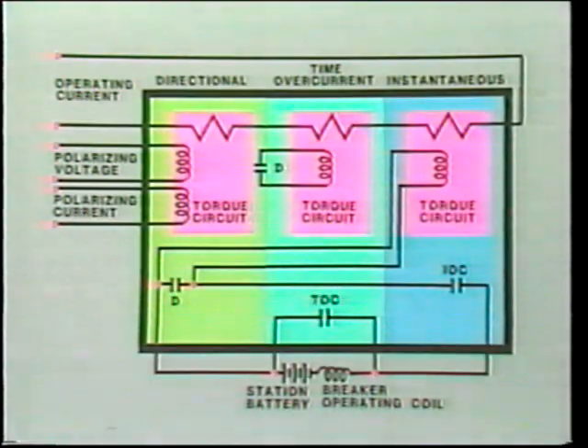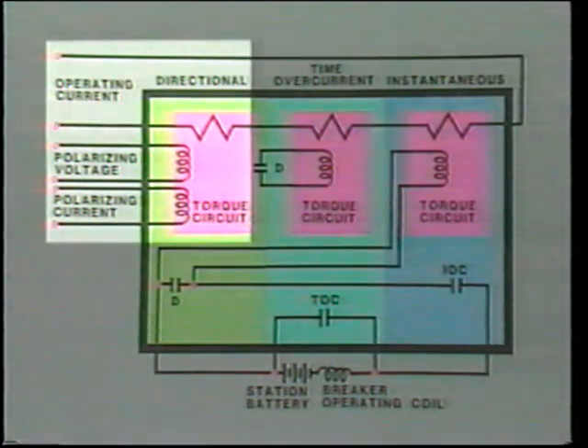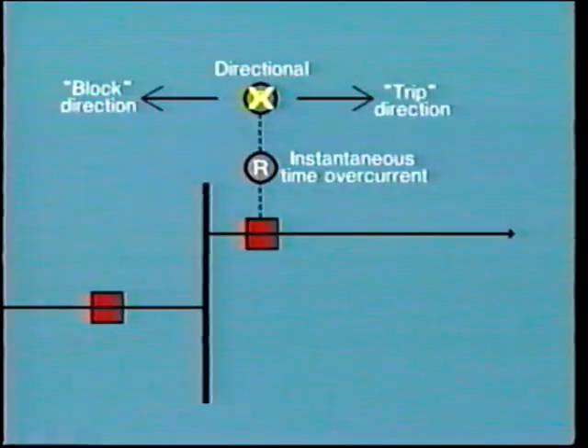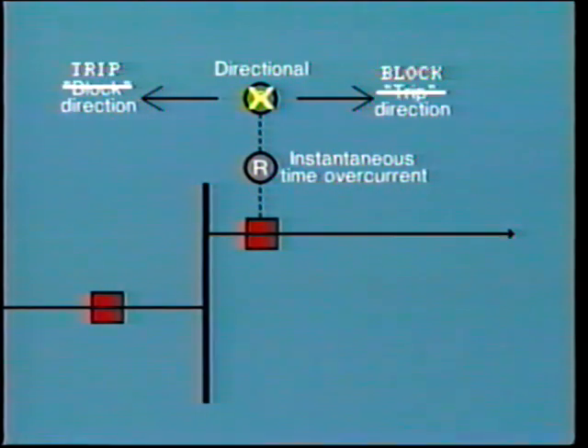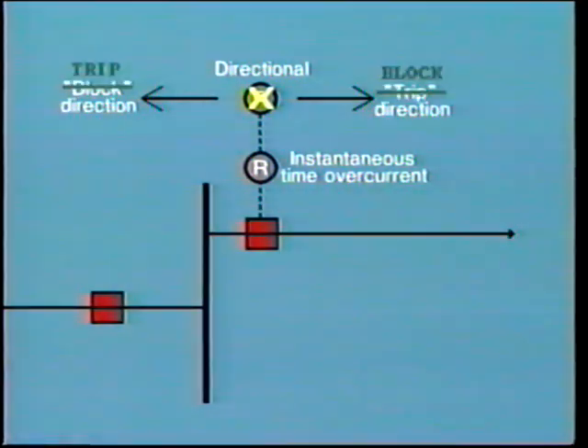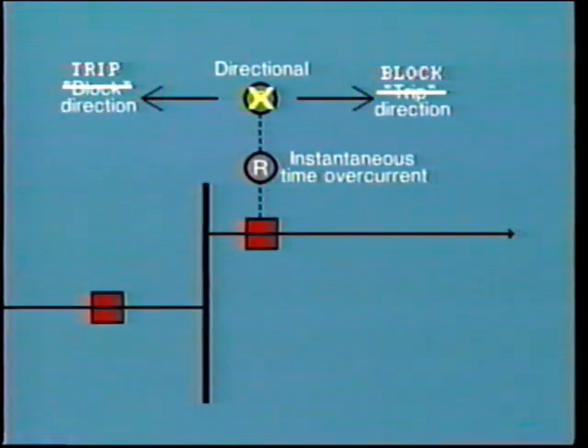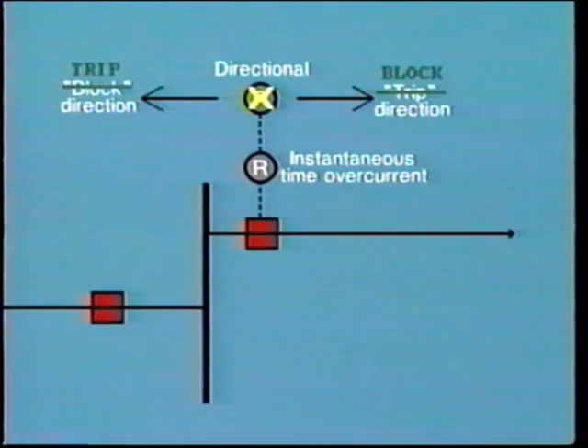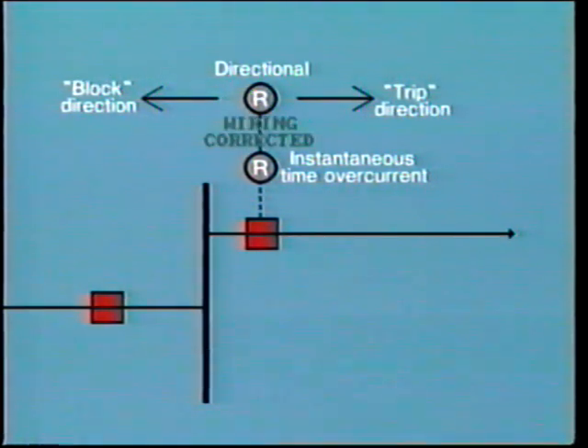Further checking revealed that the documentation provided by the relay manufacturer indicated wrong voltage connections for the polarizing circuit, and the directional element was wired this way. As a result, the relay blocked the instantaneous relay from tripping for faults in the operate direction. By the same token, it allowed tripping for faults in the non-operate direction. The manufacturer was informed, the diagrams changed, and the connections corrected.